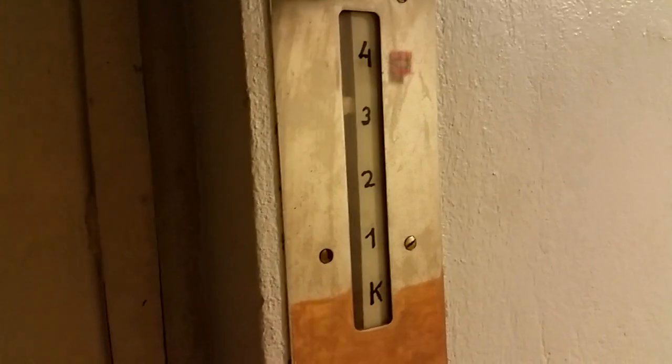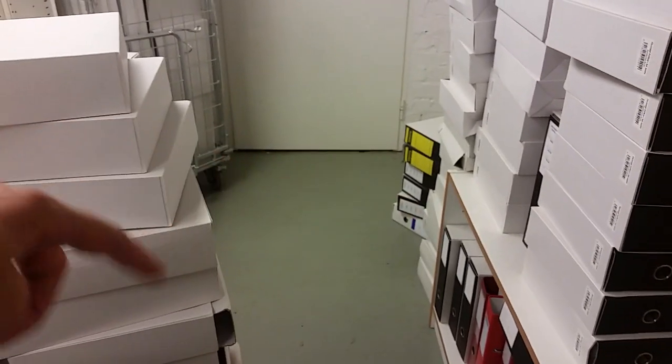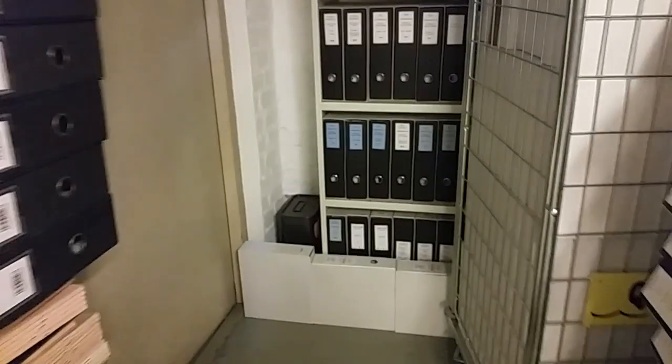You see that foot switch? That's what that is. The elevator is a bit special because when you walk in, there's a plate to put your foot on — all your weight on it — and it has a switch underneath. This keeps the light turned on, but when there's nobody in there, the light is off. It's a bit special and it's all mechanical — switches and relays. There are no level switches in the doors; the level switches are in the engine room itself. Nothing is in the elevator shaft — all level switches are in the roof in the engine room.